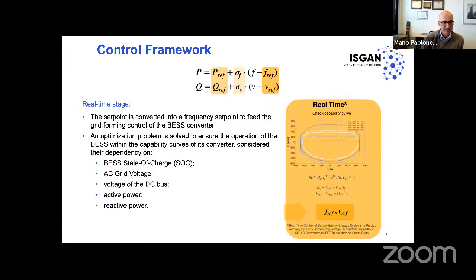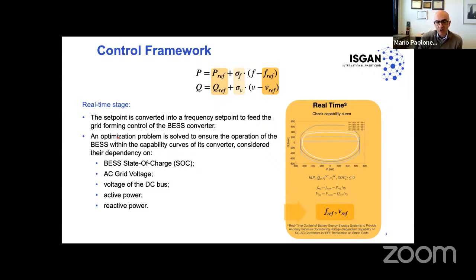Then you have the real time. As I said, the real time control stage is essentially taking into account the battery state of charge, the AC grid voltage, the voltage of the DC bus, thanks to the battery model, and the active and reactive power capability curves. And essentially, by solving an online optimization problem, it is capable of ensuring that the set points which are issued are compliant with the capability curves that, as I said, move and change according to the AC and DC voltages. So essentially what we do is embed the dynamics of the DC and AC bus voltages into the optimization problem, such that we guarantee that we are always inside the capability curves, given the actions of the converter, because these voltages, of course, depend on the power flows on the DC and AC buses.